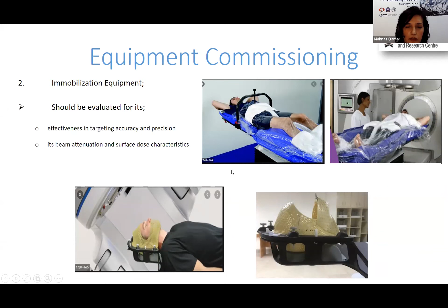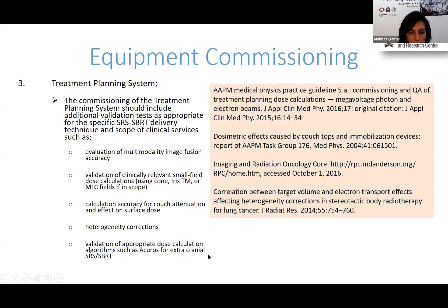Treatment planning systems. I think I'm running short on time, so I'm going to go through this quickly. The commissioning of the treatment planning system should include additional validation tests as appropriate for specific SBRT and SRS delivery. They should evaluate multimodality fusion, special validation of the small field sizes or small apertures being used, and heterogeneity correction, and also validation of special algorithms such as Acuros, which will be used for extracranial SRS and SBRT. For your end-to-end and system imaging QA, it is recommended to use motion systems.